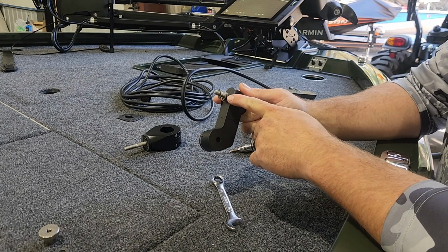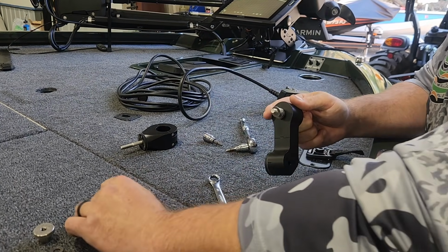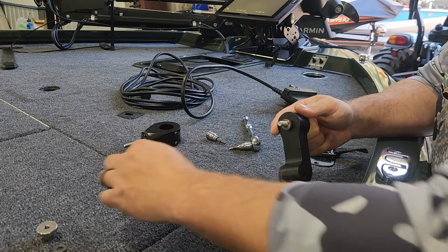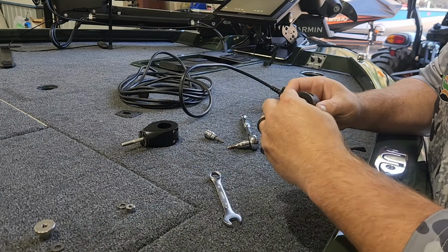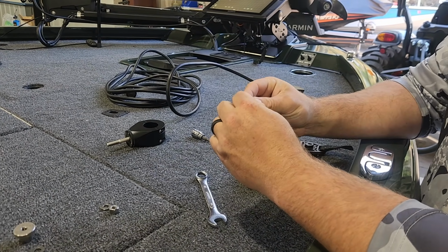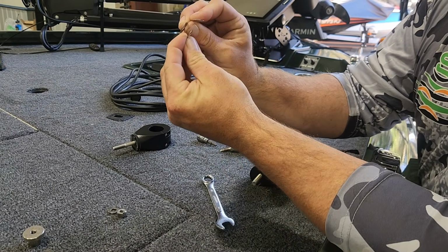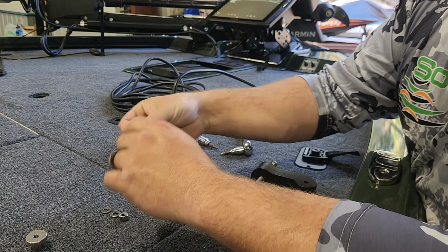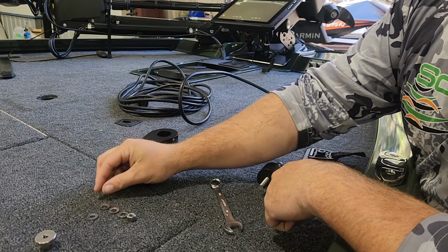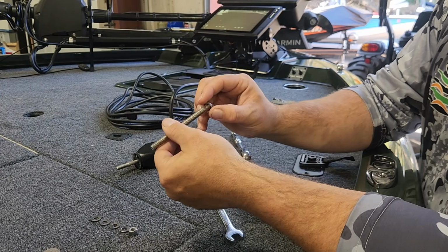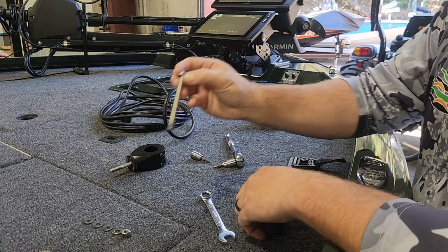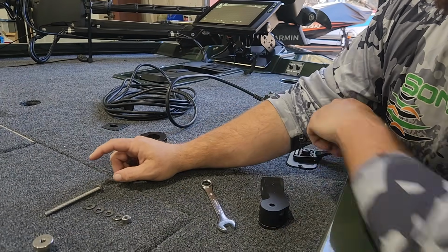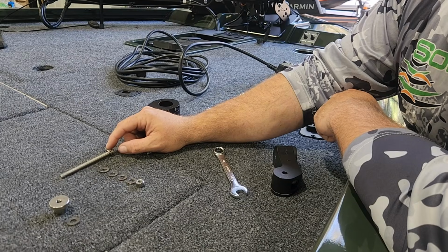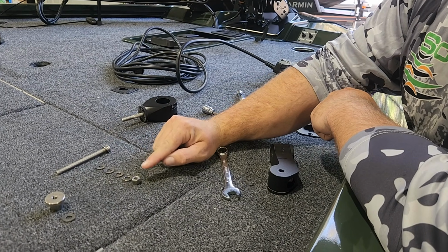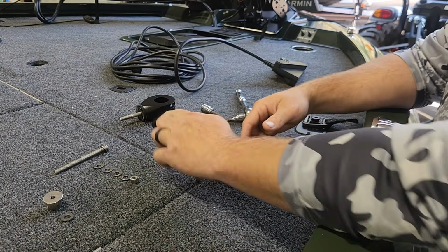This is a very important order of washers to pay attention to. We've got our locking nut, a regular flat washer, and then a set of 3 concave washers that face opposite each other — two facing one way, and a third facing the opposite direction. Then we've got the bolt, which has an outward mating washer that goes on the outside of the transducer; that can stay on the bolt. So again: bolt and transducer washer, our 3 concave washers, flat washer, and lock nut, all separated — and then we've got our arm mount here.